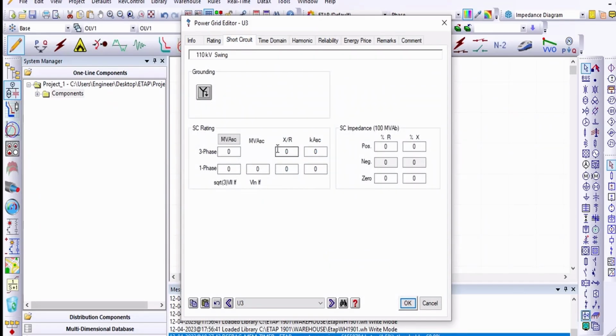For the short circuit, now we can put here whether it's grounded or delta. I would like a grounded connection, or you can select the delta here, and this time we can go for the Y connection. We may not need it for one phase because they will be automatically calculated. You can toggle how you want to model the short circuit, based on MVA or kVA. You can insert the short circuit power directly, input the volt-ampere, or input just the kilovolts.